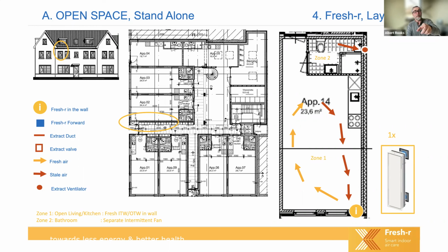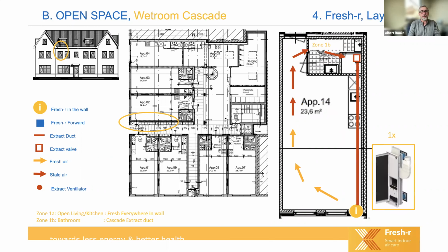And you see up in the upper right-hand corner, there's still a bath fan. That's how the bath exhaust is done. We haven't touched it. We've just added fresh air to that building. Next scenario, we do the same thing and put it in the same place, but we run some ducting to the bathroom. Now we're picking up the bath, and we got rid of the bath fan, so we got rid of the energy penalty. We improved the bath, because continuous ventilation creates a better bath environment, since it always dries out the room. There are lots of good things we can talk about separately. And so that's the device.